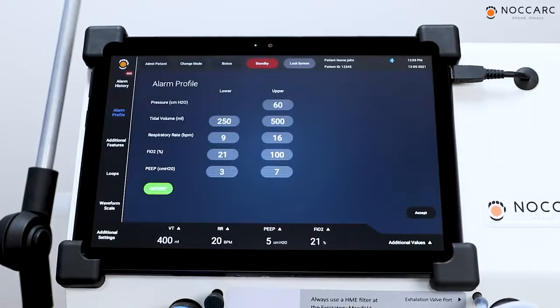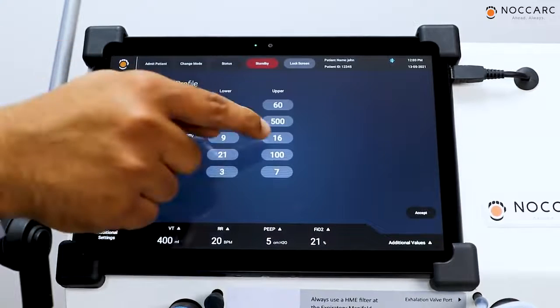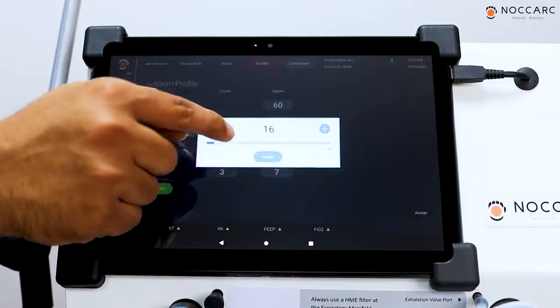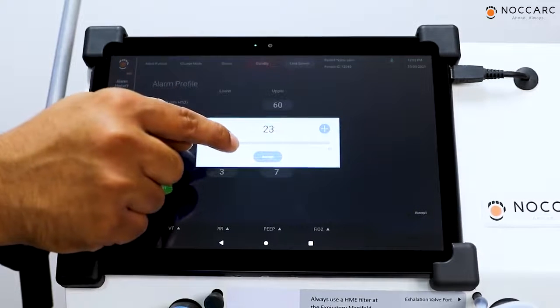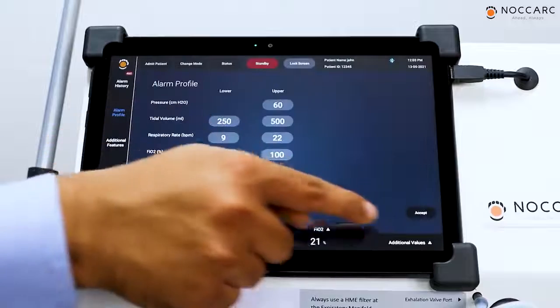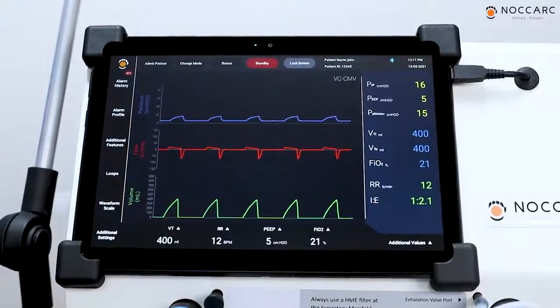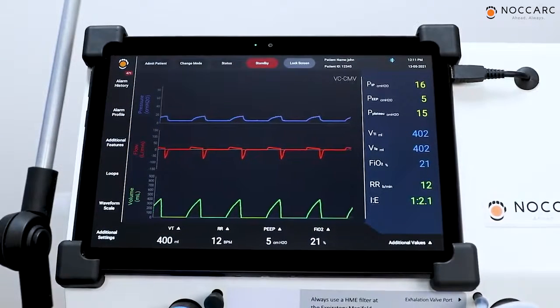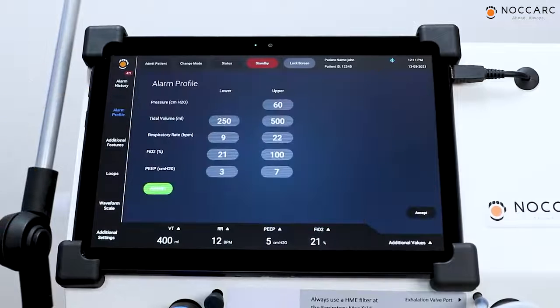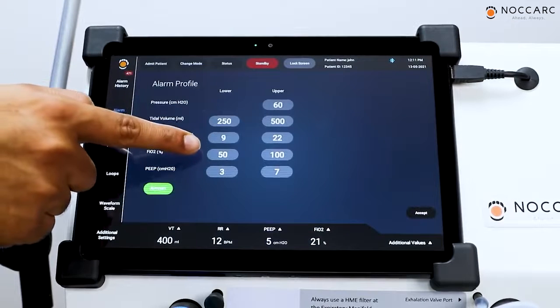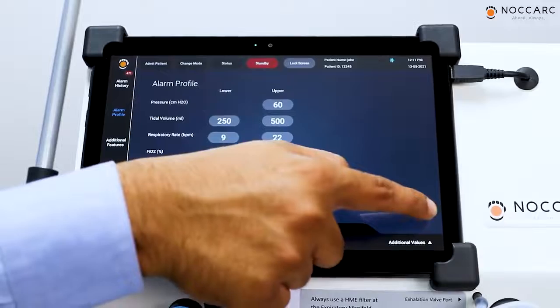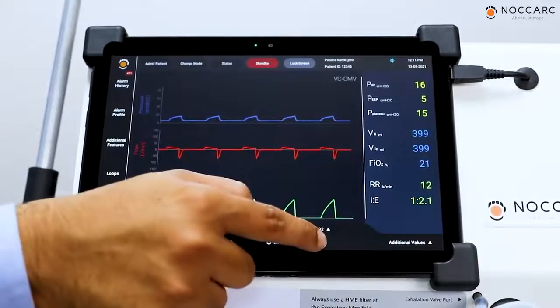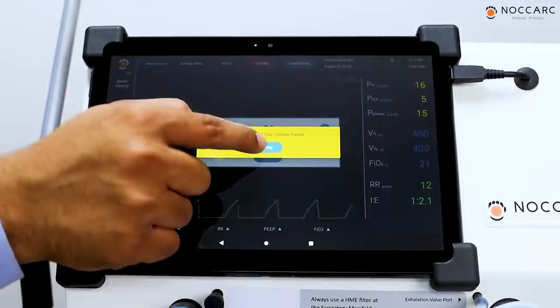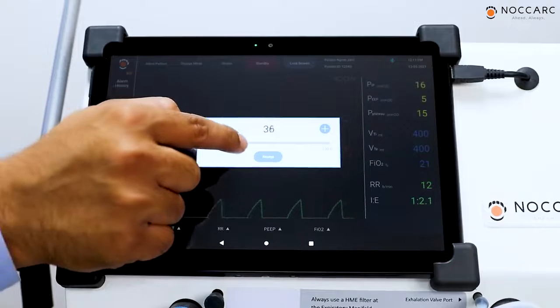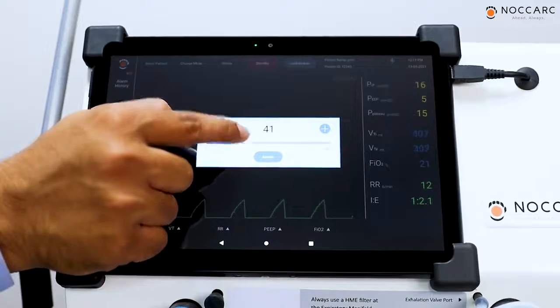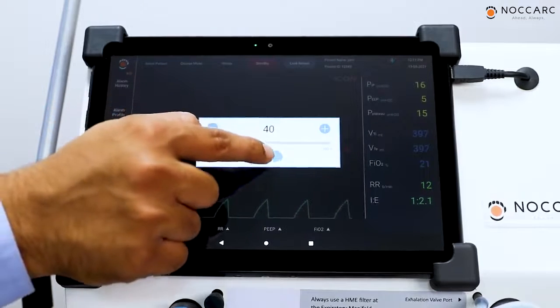Press on alarm profile and increase the upper limit for RR more than set RR value. Press on accept. To test low FiO2 alarm, press on alarm profile. Here you can see lower limit for FiO2 is 50. Press on accept. Now press on set value of FiO2. Keep this value lower than 50 and press on accept.